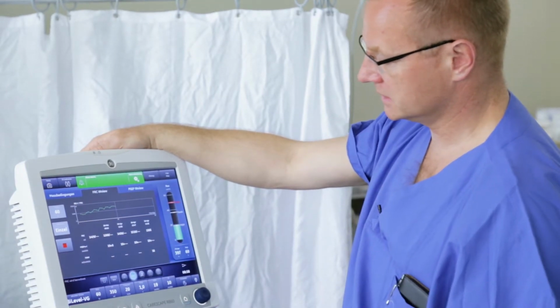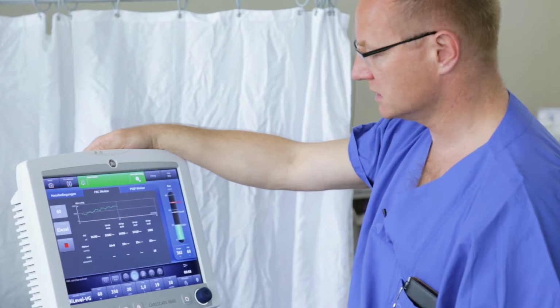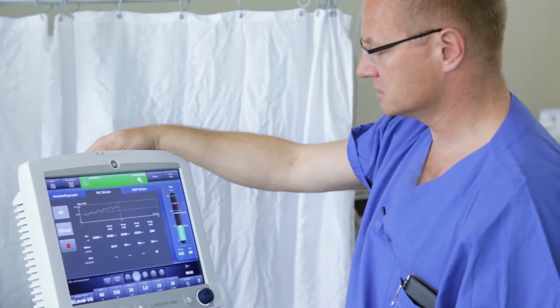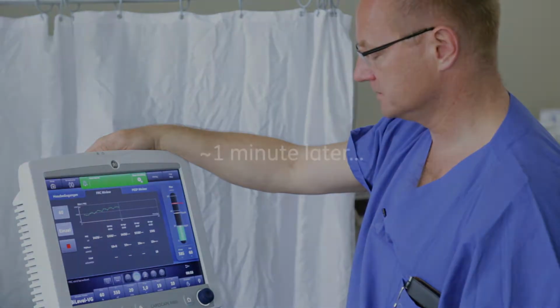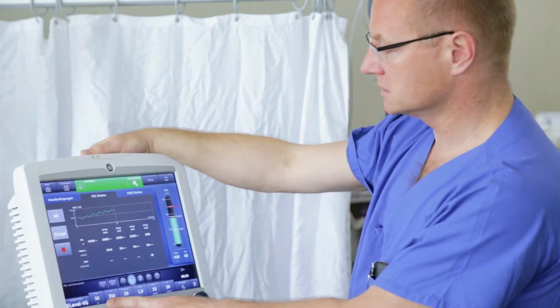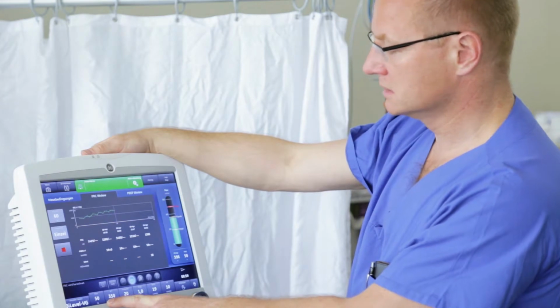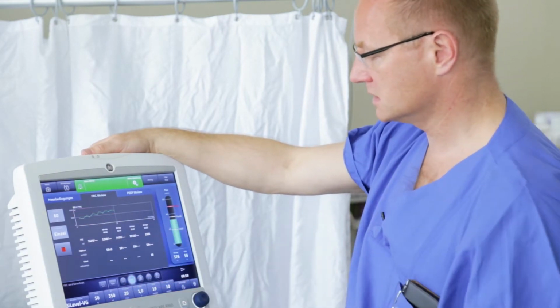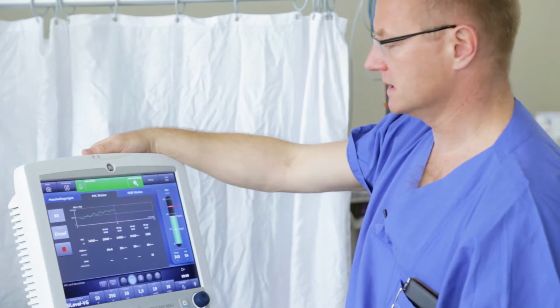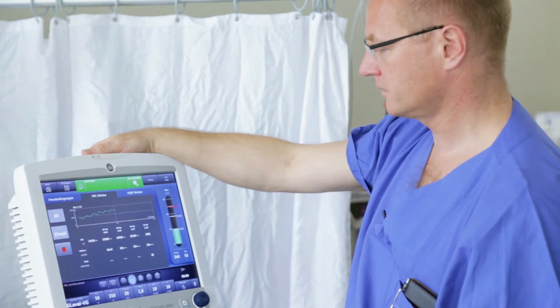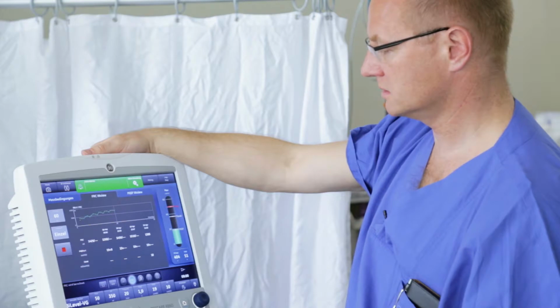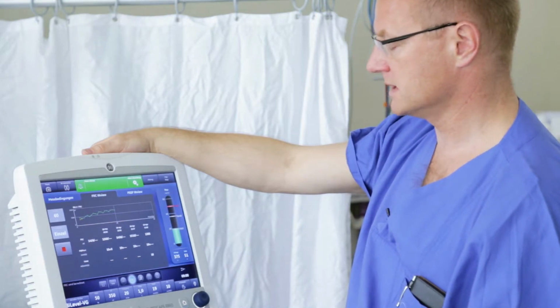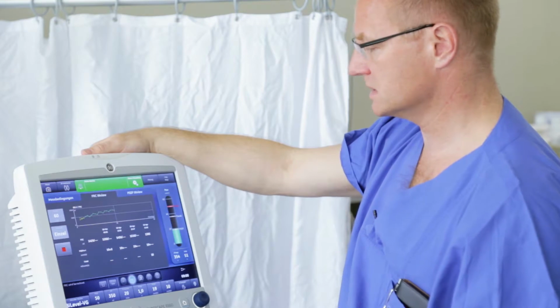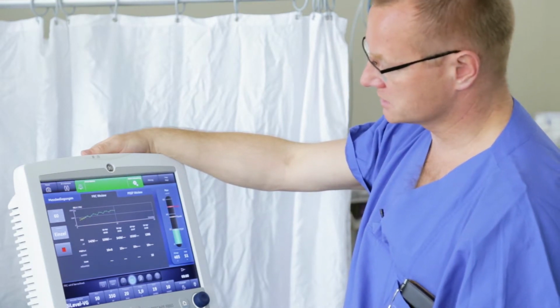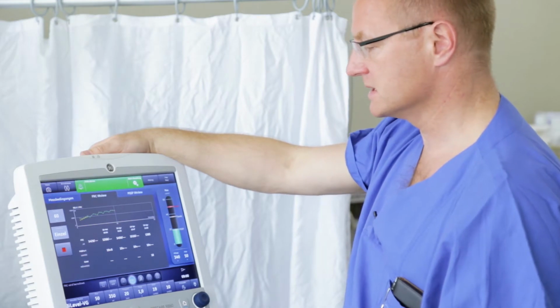The device will now reduce the inspiratory oxygen concentration back down to 50% and then take a second FRC measurement in the washout phase. The inspiratory oxygen concentration has now declined from 60% back to 50%, and the second measurement has begun within a few breaths. And here we are already seeing the first value of the second measurement as a yellow dot. It will now be another 20 to 25 breaths before the inspiratory oxygen concentration is readjusted and the second measured value is read out.